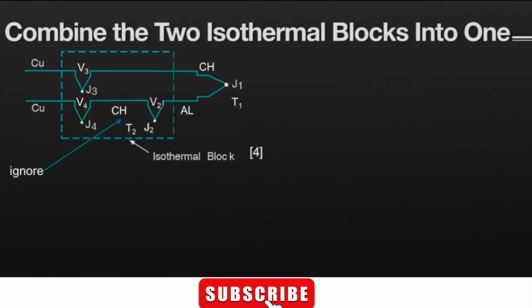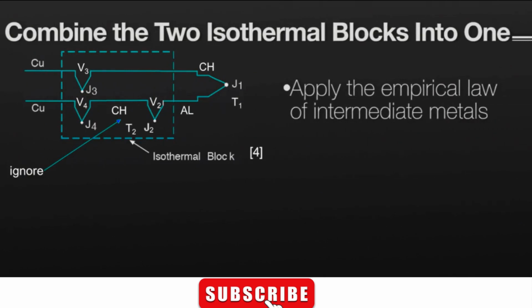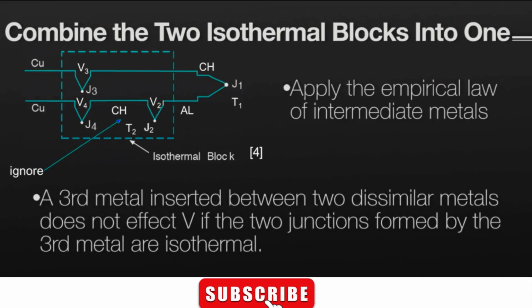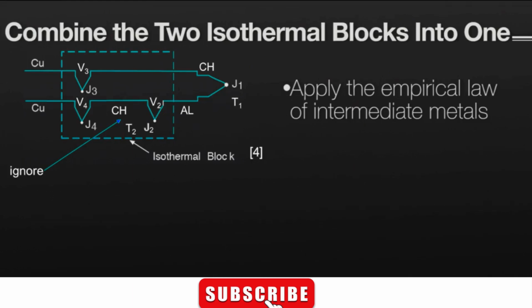This is the part where we combine the two isothermal blocks into one big one. Have you ever heard of the empirically derived law of intermediate metals? I didn't think so. Well, guess what? Before I studied thermocouples, I never heard of it either. But anyway, this law of intermediate metals says that when you insert a third metal between the two other dissimilar metals at an isothermal block, your thermoelectric voltage won't change. So let's apply this to our big isothermal block. What this means is we can ignore the chromel connector wire between junctions J2 and J4. And the system will function the same as if that alumel wire on the right was connected directly to the copper wire.